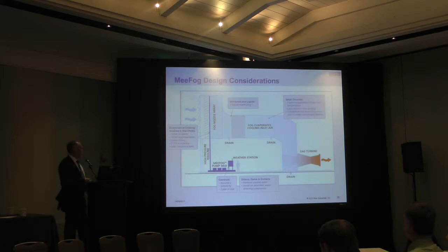So controls accuracy is important too. GE used to have this spec that you wanted to have not more than 99% or 98% humidity at the inlet here, so you would be assured of not having excess water. We're controlling by measuring the ambient weather conditions and calculating how much water needs to go into that air mass flow to reach the target temperature.